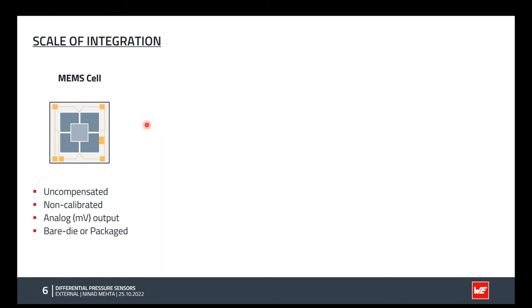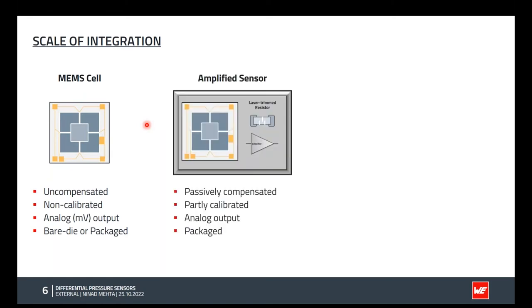So these things, at the end, the application needs to take care of. Another type is the amplified sensor. So now, with the measurement MEMS cell, we have the amplifier, which amplifies the output signal. And also in some cases, we have passive compensation, with laser trim resistors, where you do the temperature compensation of the output at a fixed temperature. So usually these are both calibrated and compensated, but in applications where a dynamic temperature is used or there is a big difference in temperature, then this sensor might not have accurate output at all temperatures, because the passive compensation has a very narrow temperature window.